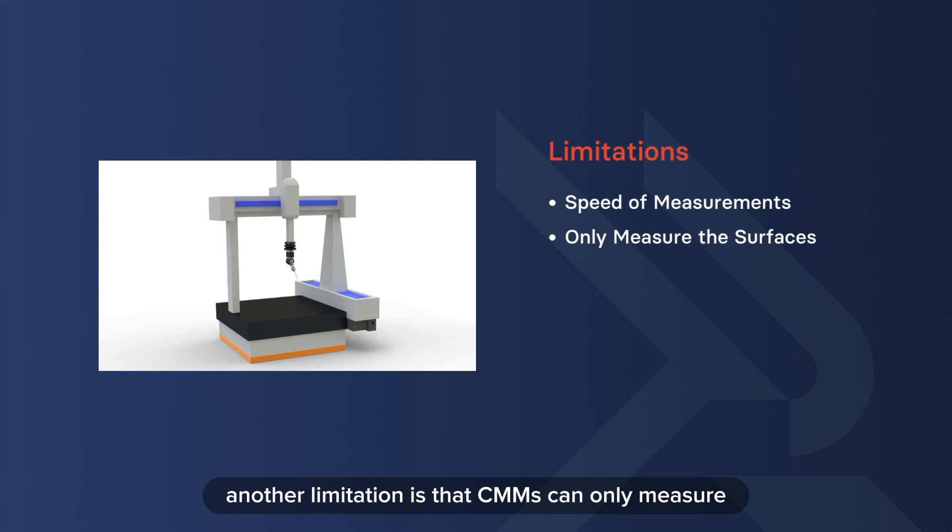Another limitation is that CMMs can only measure the surfaces they can physically touch with the probe. So, the probe tip size must match the features intended for measurement. If the tip is too large, it won't effectively capture finer details and internal features in complex parts.